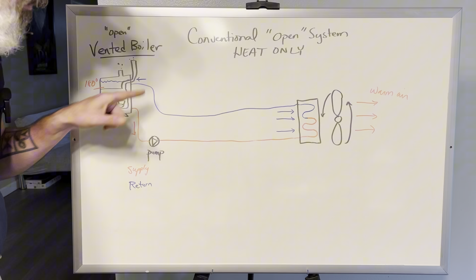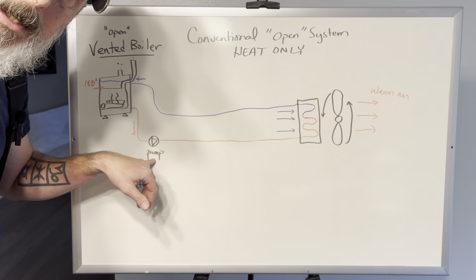What I'm showing here is that your boiler manufacturer will tell you where you need to pipe from - they'll say pipe from here or there, so on and so forth. But most times, in my opinion, I'm going to tell you to pull from the bottom. That's right, I said most of the time you'll want to take the boiler water from the bottom of the boiler.